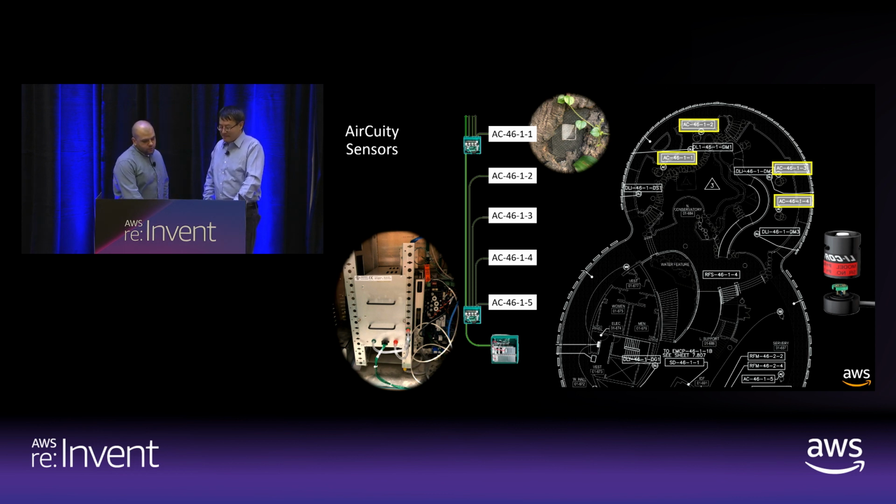That's right. And we also have quite a few of these instantaneous light sensors distributed in the building. Those are the ones labeled DLI, which I haven't highlighted here, but they look something like this on the right-hand side. So we're basically getting, I would say, 4 different types of data reliably from all these zones: CO2, relative humidity, dew point temperature, and instantaneous light.